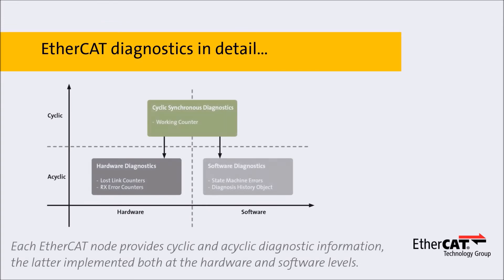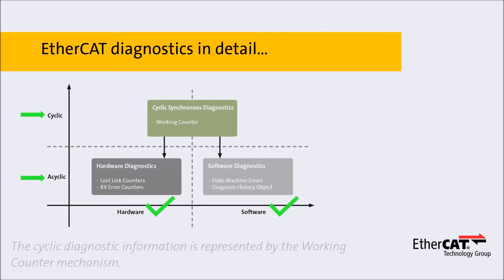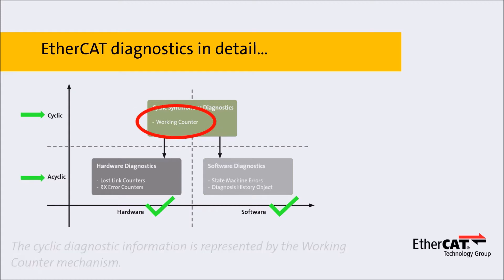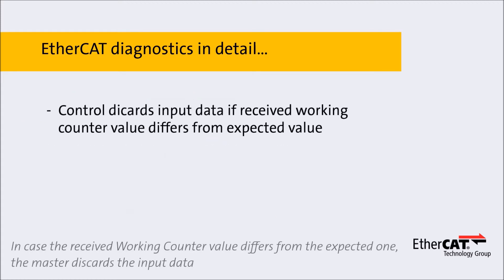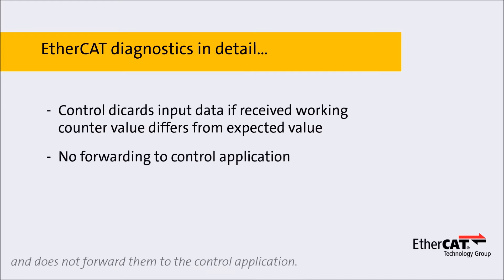Each EtherCAT node provides cyclic and acyclic diagnostic information, the latter implemented both at the hardware and software levels. The cyclic diagnostic information is represented by the working counter mechanism. In case the received working counter value differs from the expected one, the master discards the input data and does not forward them to the control application.